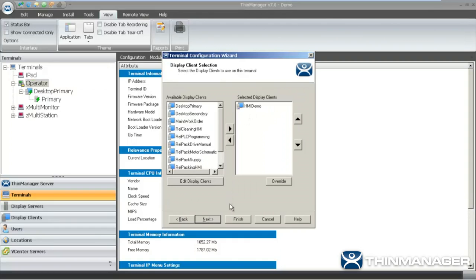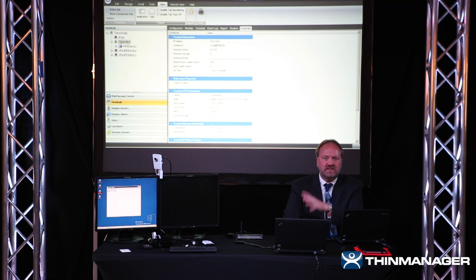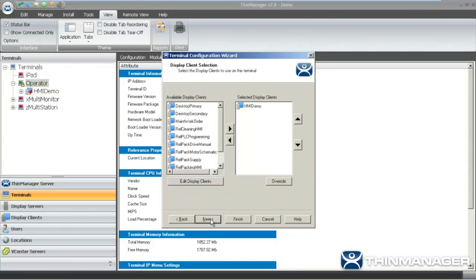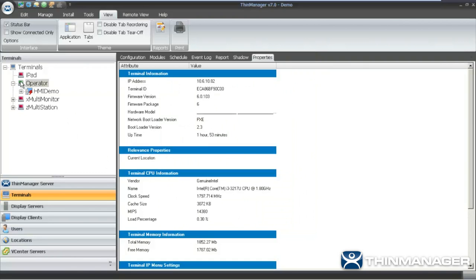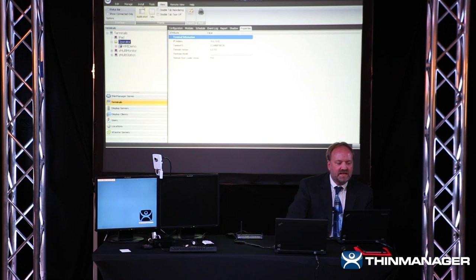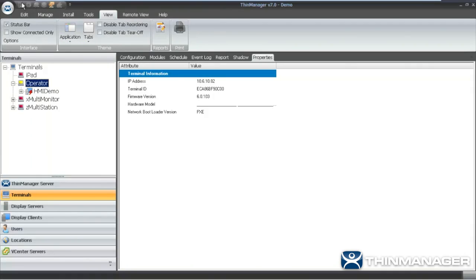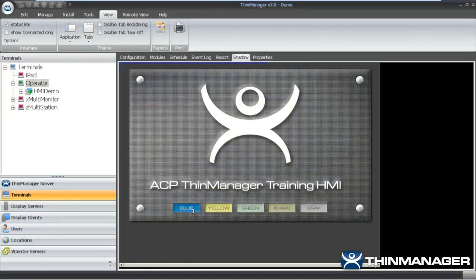I made the change through the wizard — moved forward until I got to the display clients, removed Desktop on Primary, added HMI Demo Application, and applied it to the terminal. To push the configuration change to the terminal, I restarted it. In 7.0 there are quick access icons across the top: instead of right-clicking to restart, I could have just touched the quick access restart button. Now I'll switch over to the shadow and start the HMI visualization interface, which is running on both the primary and secondary servers simultaneously.